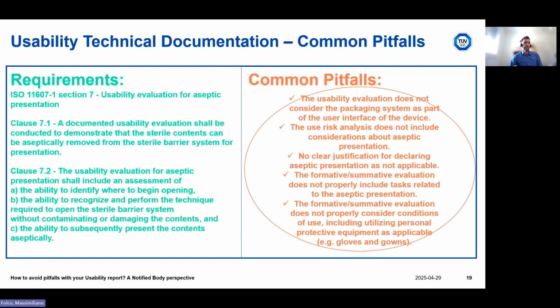So the aseptic presentation is embedded in the definition of a sterile barrier system. So when you have a sterile barrier system, you have aseptic presentation, at least for the contact between the sterile device and the not sterile part of the sterile barrier system. At least this is applicable. Then sometimes we find a justification from the manufacturers that states that aseptic presentation is not applicable to their devices, but at least for this aspect, so the contact between the sterile device and the not sterile part of the sterile barrier system, the aseptic presentation is applicable, even if the device is to be used in a not sterile field. At least an evaluation of the aseptic presentation shall be done.